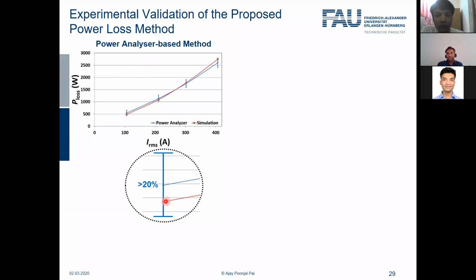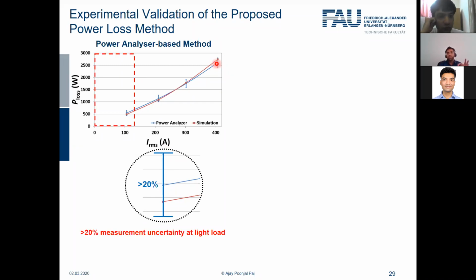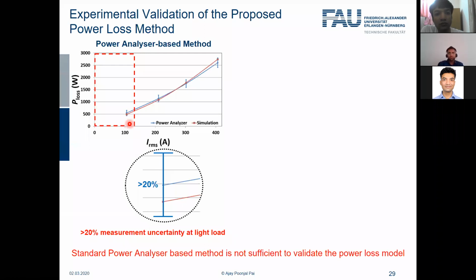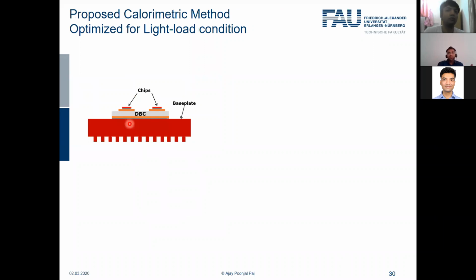But if you look here, the message is that the simulation is still within the tolerance of this measurement method for almost all the points, from light load all the way up to nearly nominal current. So there are two messages. One is that the simulation is matching the measurement. This was the main goal for us, to verify the measurement method. The second is that this measurement method based on the power analyzer has a high uncertainty, which could be in the range of 20% at light load. So the standard power analyzer based method is good to measure with, but it is not sufficient to validate the power loss model. Therefore I need a second method to measure, and the second method was developed as part of this thesis.